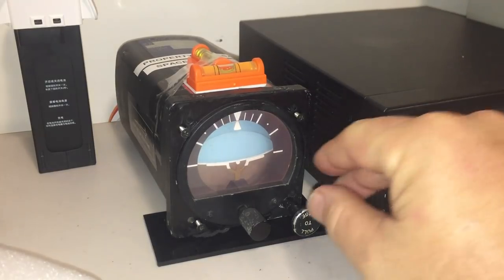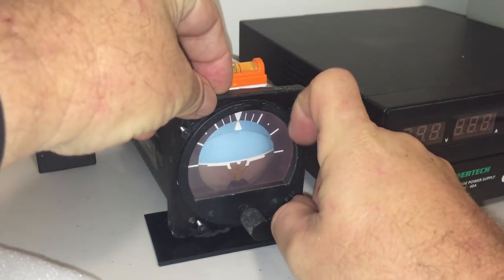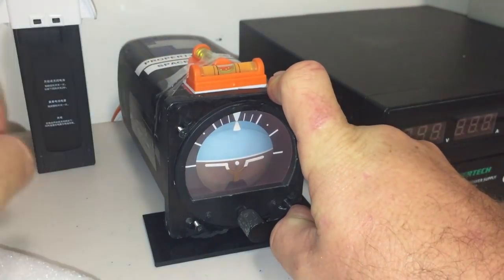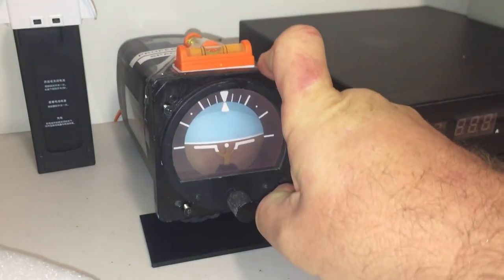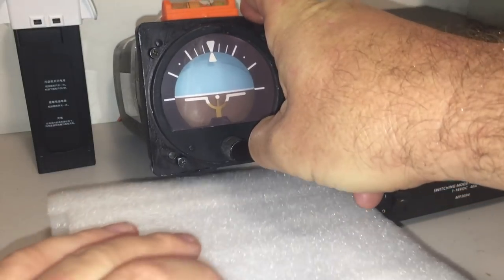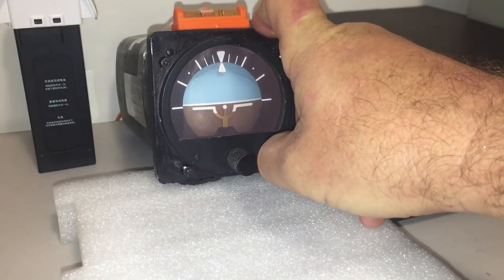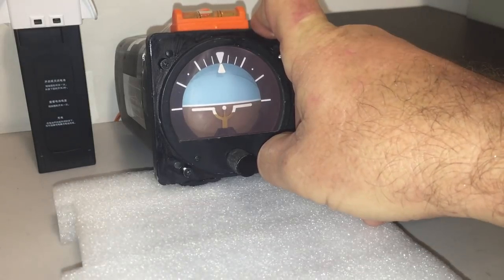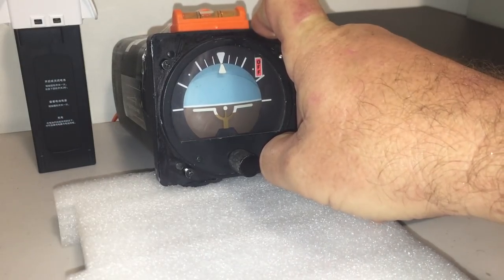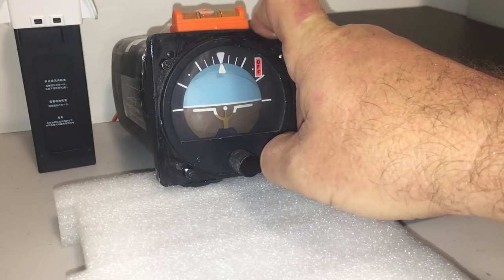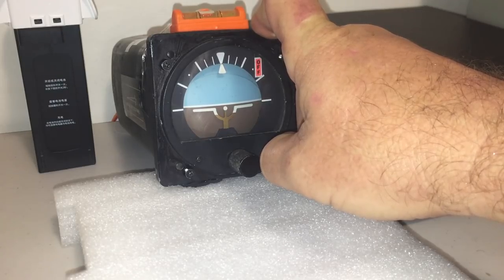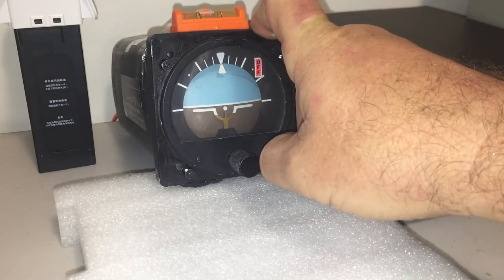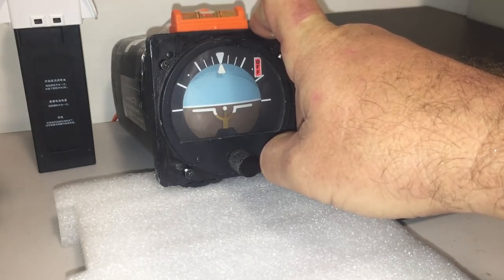So the request was to cage the instrument. So it's now caged. I'll hold it caged and raise it up about 20 degrees, which I've done. I'm holding the cage. Now I'm going to turn off the power and I'm holding the cage until the gyro stops completely, and that's going to take several minutes. So we'll just have to wait.